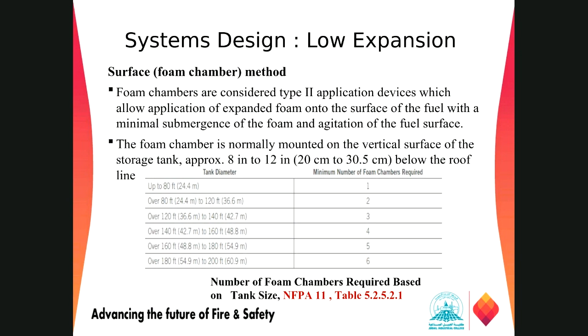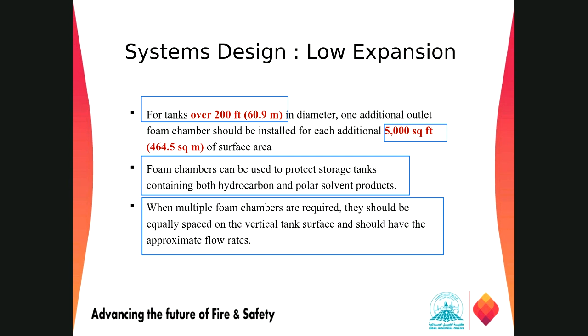So this table is up to 60.9 meters or 200 feet. If the diameter of the tank is larger than that, more than 200 feet, then for each additional 5,000 square feet we need one additional foam outlet. Foam chambers can be used to protect storage tanks containing hydrocarbons or any kind of polar solvent products. When multiple foam chambers are required, like 2, 4, 6 or so on, they should be spaced equally, based on the flow requirement to protect against the fire.